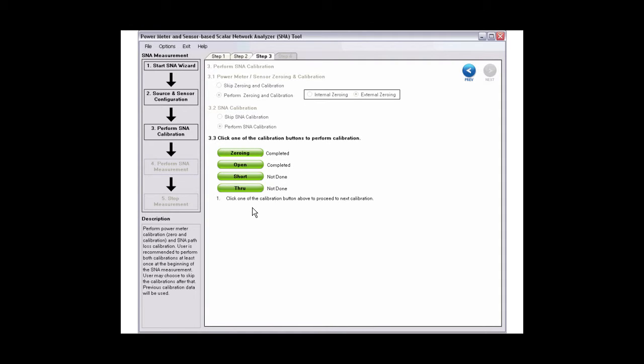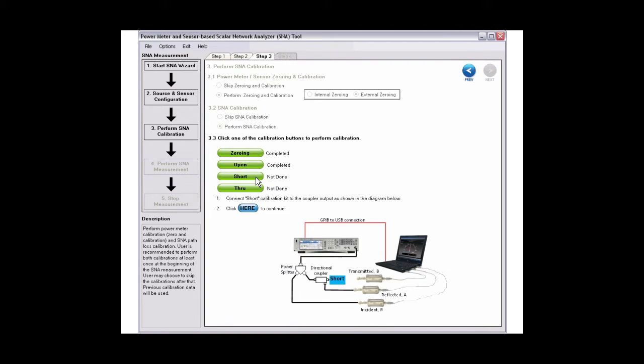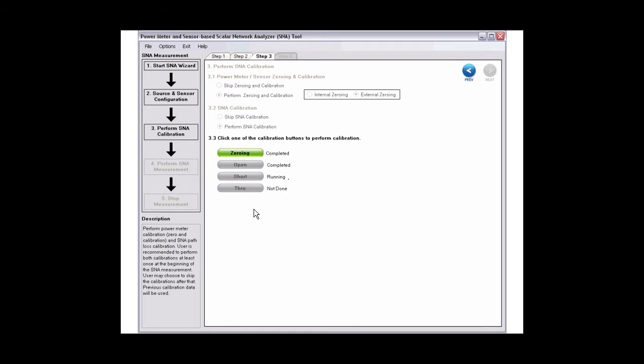Once done, continue with short calibration. Click short, then connect the calibration kit according to the diagram. Click the button in step 2 after you have connected the calibration kit.